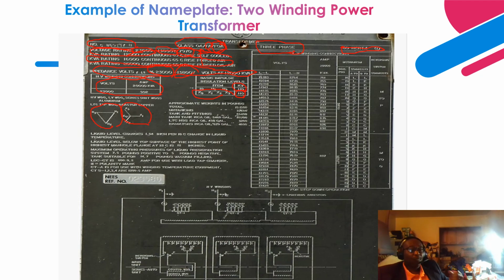So for the load tap changer, the load tap changer has on-load tap changer connections. It utilizes a reactor or preventative auto transformer. Basically, that is more of a reactor that allows all the taps to be achieved. So this is the load tap changer, on-load tap changer.